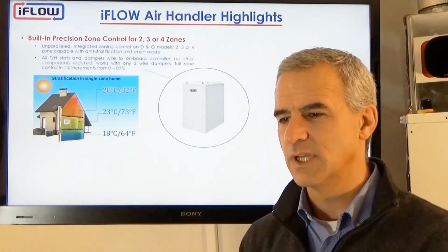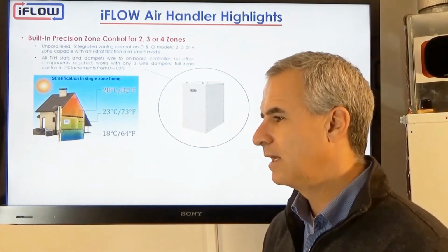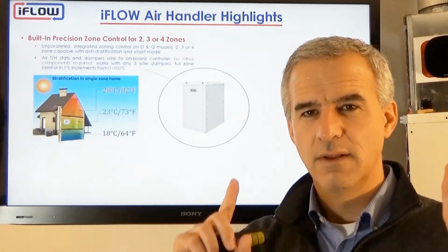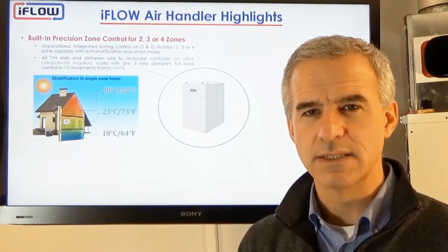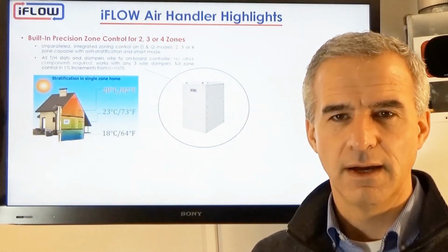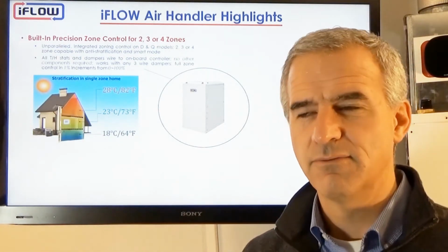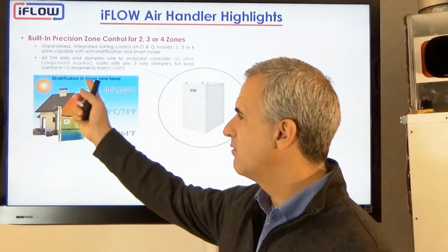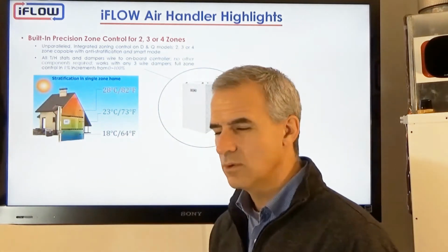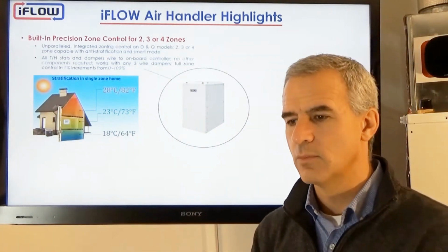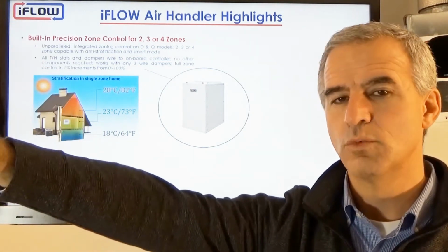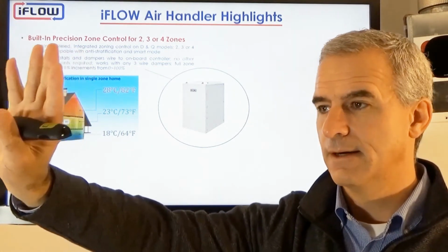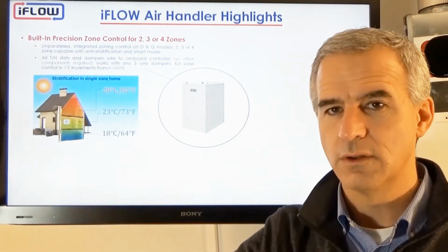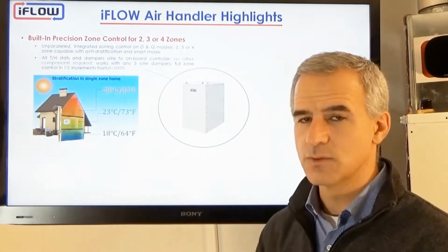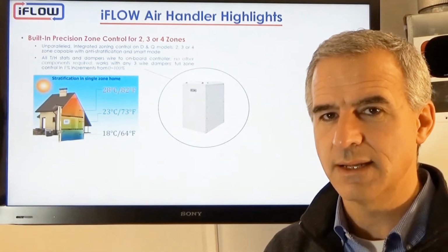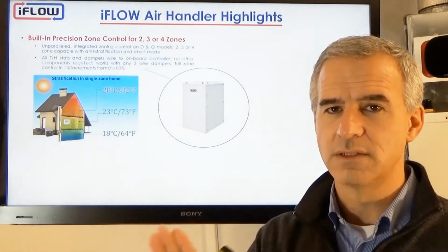Redoing that in an existing home might be a little bit difficult, but in a renovation situation, again, we can still put the zone dampers into your existing system in many instances and use the common return and give you at least the supply control for the system. So with that, we can solve many of the stratification issues with zoning. We can solve the remote room issue, where the room over the garage, for example, is notoriously hard to control. It'll be hot in the summer, it'll be cold in the winter. We can deal with that. We can set that as one zone. It has its independent thermostat and delivers all the heating and cooling that room needs to make it comfortable and usable.